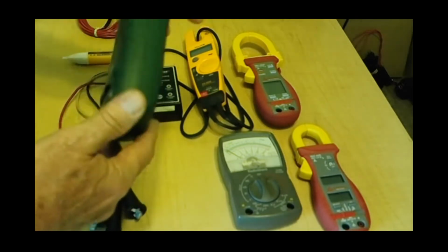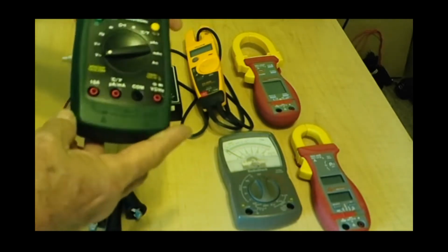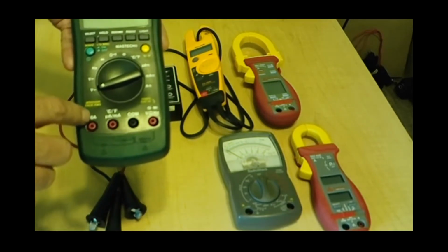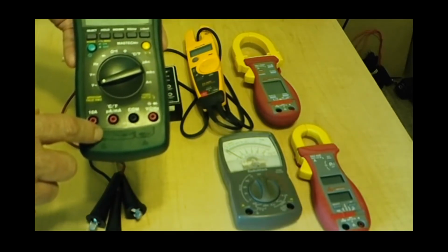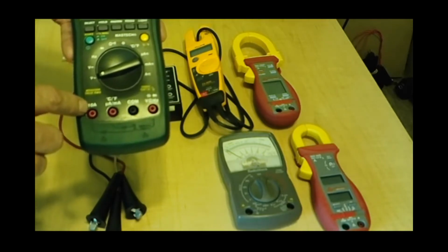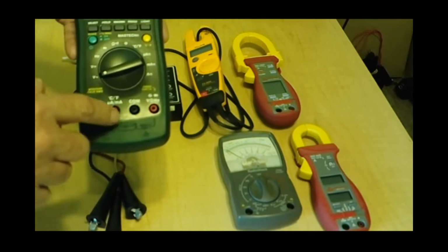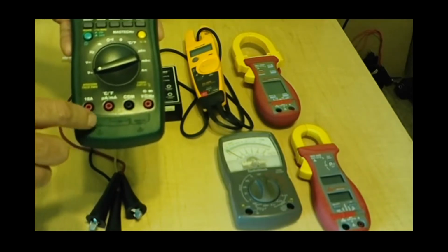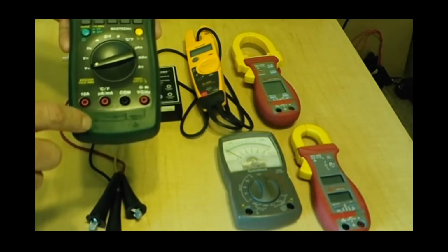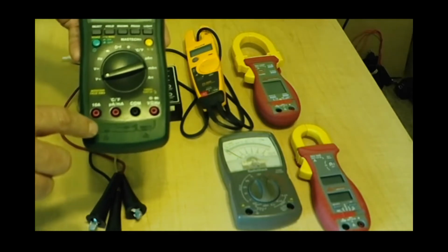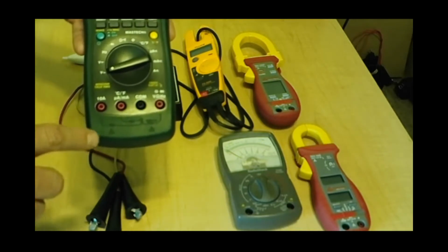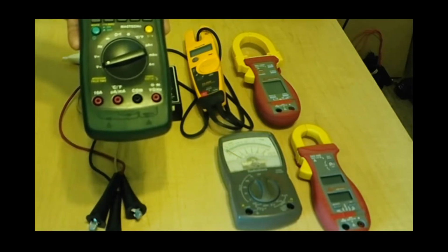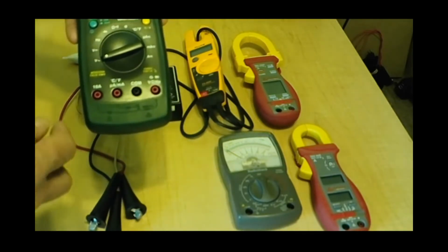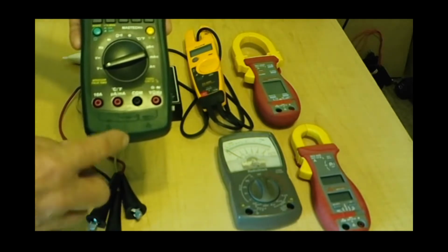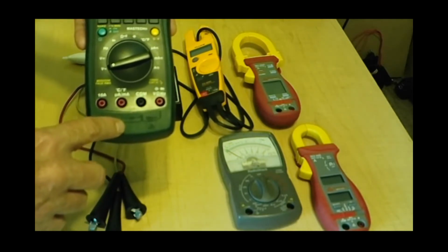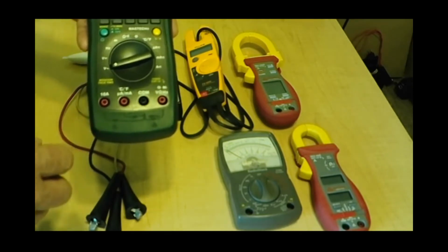Now the fuses that are in the back of the meter, those fuses right there, there's two of them, one for 10 amps, one for 1 amp. Those fuses are high energy specialized fuses. If you ever pop the fuse in the meter, do not replace it with a standard fuse. They have to be high energy fuses that can withstand the short circuit currents at that point you're measuring. So they are specialty. You're not going to find them in hardware stores. You'll only find those fuses in supply houses.